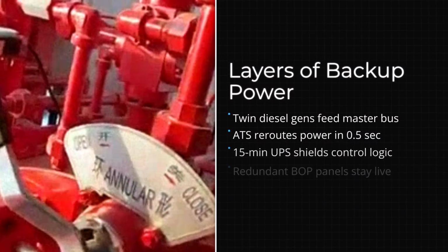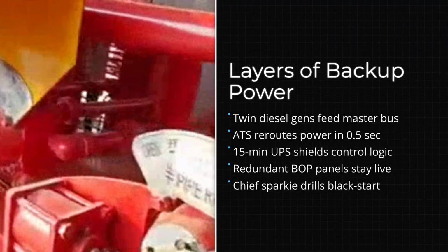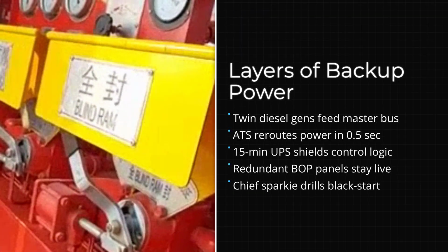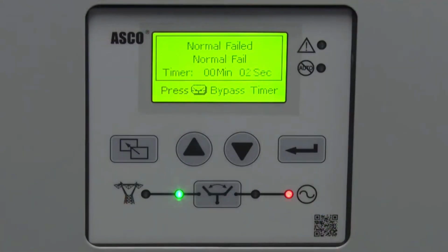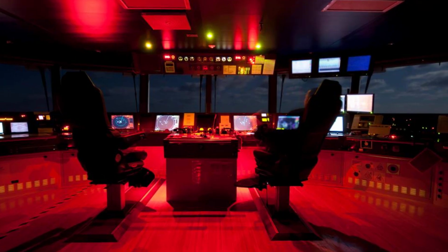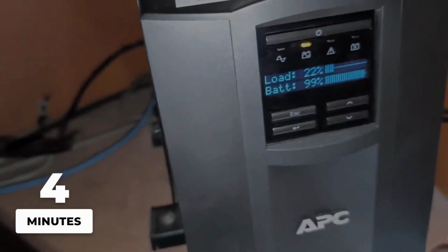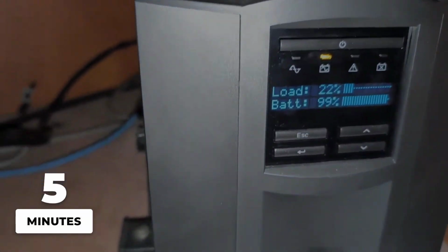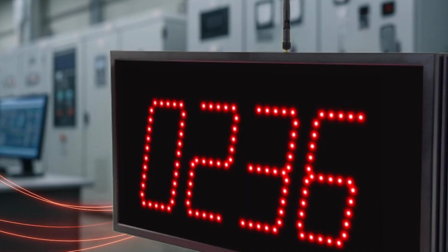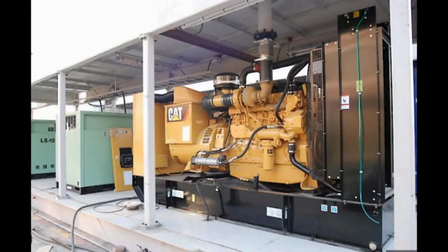For the most critical systems, control room logic, blowout preventers, and fire pumps, a dedicated emergency bus isolates these loads from the rest of the network. In the event of a total blackout, an uninterruptible power supply bridges the gap for up to 5 minutes. This window is designed to hold the line while the black start generator comes online.